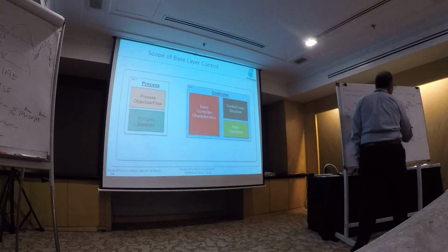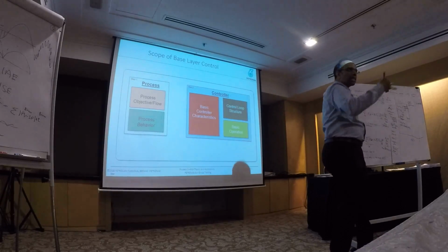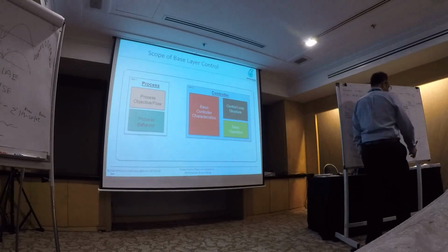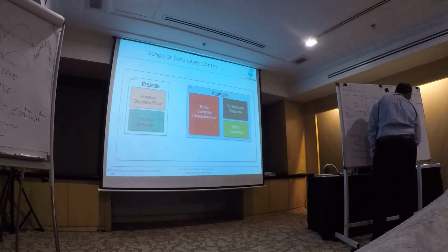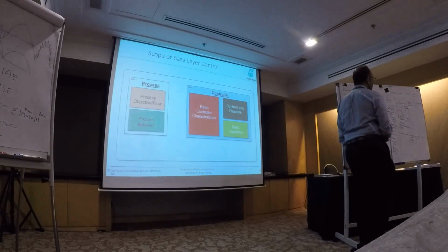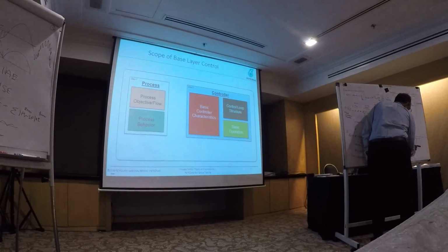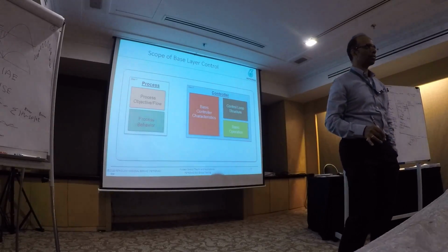The solution here is called gain scheduling, meaning I schedule when the gain is going to change. This is still within DCS. APC could solve some of these, but even for nonlinearity, APC would have a problem. APC is linear, by the way, so severe nonlinearity APC cannot handle.